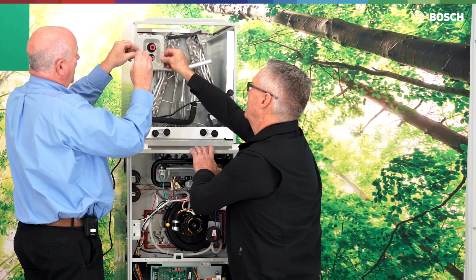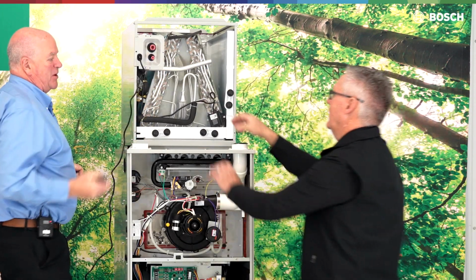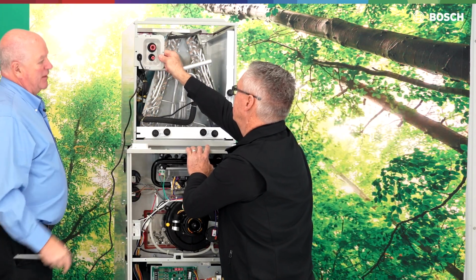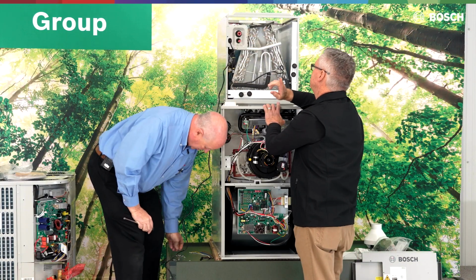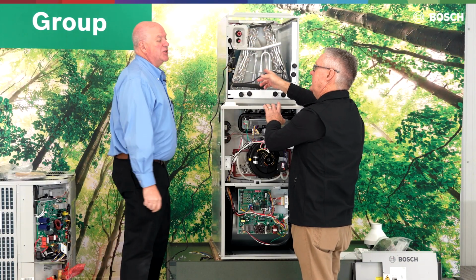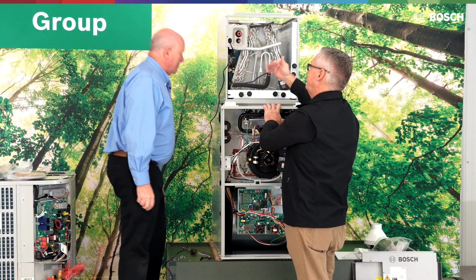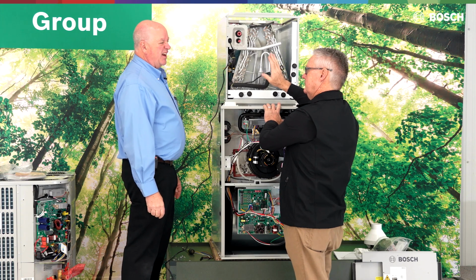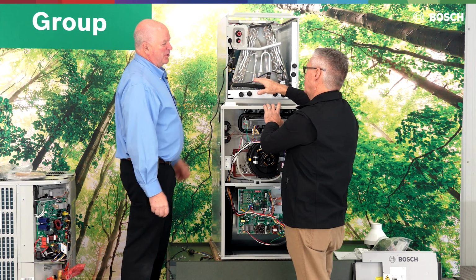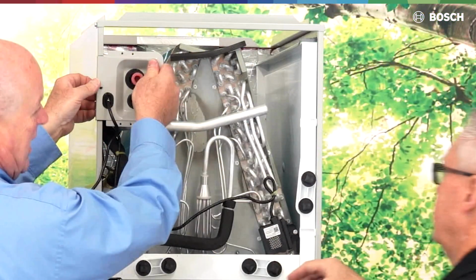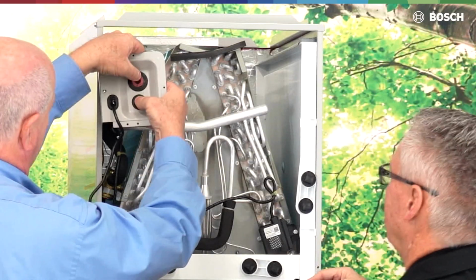Now wait, before you pull that red tip off, what does that represent? I wasn't going to pull the tip off. What does that represent? These coils should be sealed and filled with nitrogen. Yeah, not propane. Not butane. Not air. Just nitrogen. Not 410A. Not R-454. Not R-22.